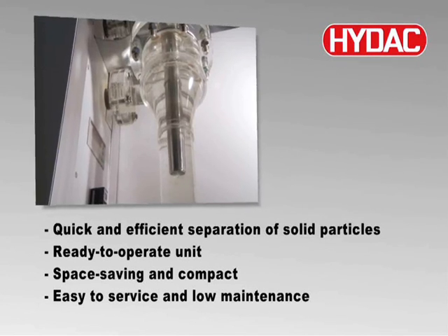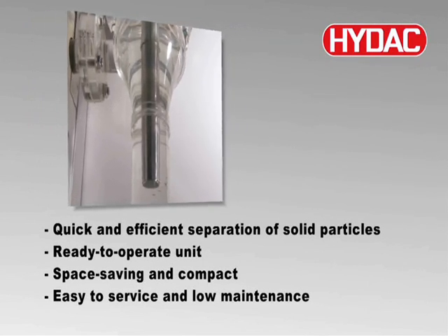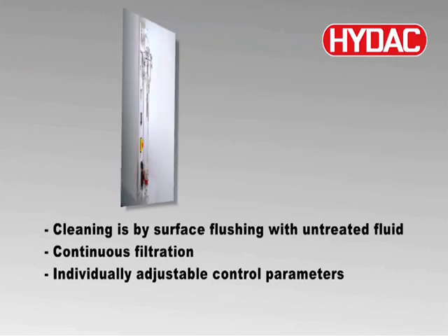The comparison with sand filters is similar. Large space requirement, high maintenance, and relatively high back-flushing quantities do not apply in the case of the ATF. To clean the filter element and housing, the entire flow of untreated water is used for just a few seconds. The cleaning intervals can easily be adapted to suit the individual process using the timer control.